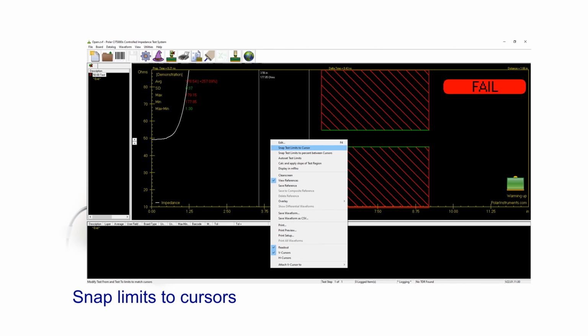If you want to set the test limits into a good place in the middle of the trace, away from the start and the end, you can select the vertical cursors, and then you can snap the test limits to the cursor. So that makes it nice and easy to set an area of the test limits away from the launch of the probe and away from the end of the trace.